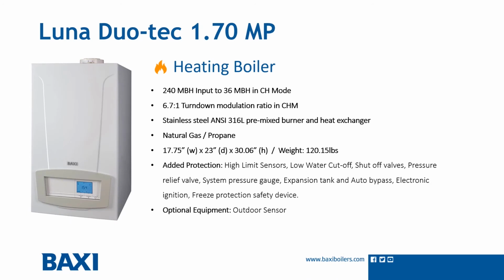The MP 1.70 is our smallest light commercial unit. It has a BTU rating of 240,000 to 36,000 for your central heating needs. This unit does not have the gas adaptive technology, but is still field convertible from natural to LP with no additional kit required. The MP 1.70 has a turndown ratio of 6.7 to 1. The unit is 17 inches wide by 23 inches deep by 30 inches high and weighs 120 pounds.